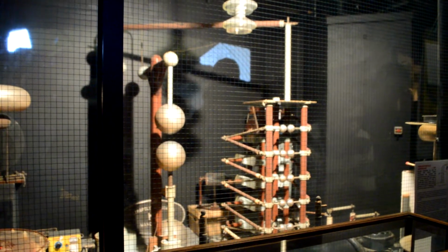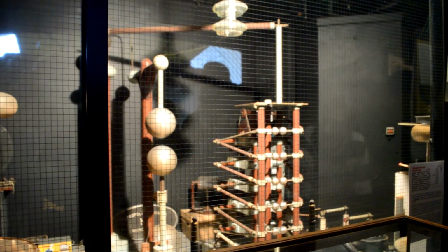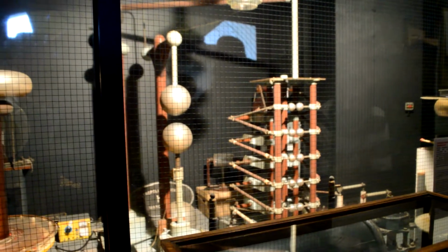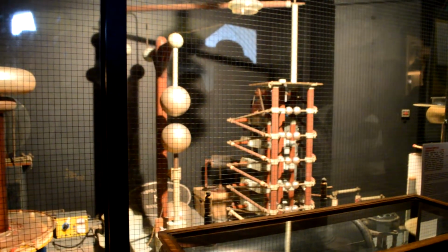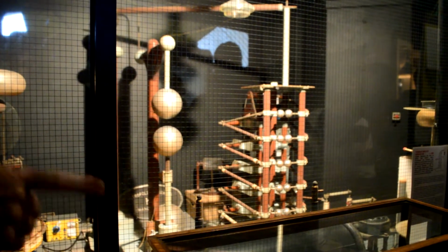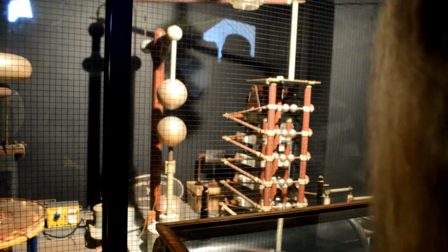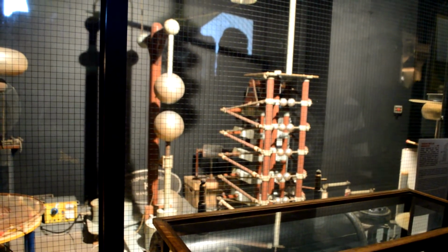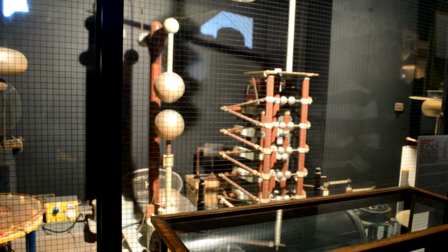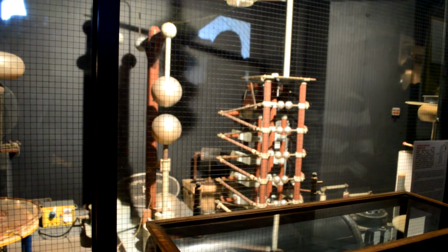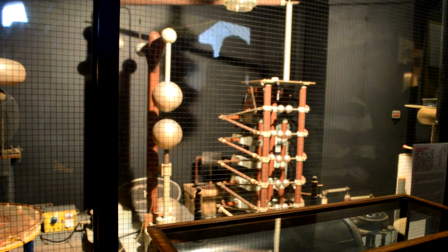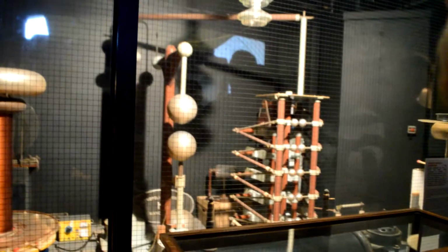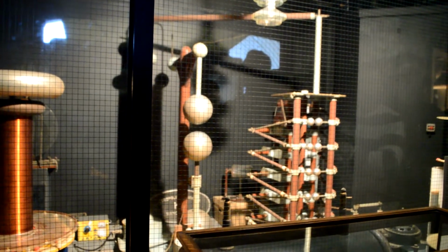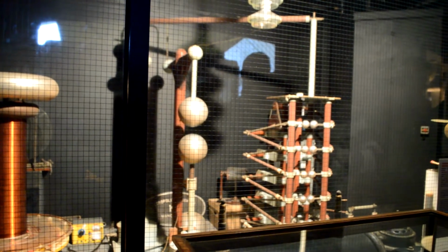International standards still exist, and I always get this wrong because it's changed, but if you look at the thing in a graph or an oscilloscope representation, the principle is that by adding a second set of resistors, which you can see on the schematic diagram on the bench, not only do you control the discharge time, which is to do with the resistance and capacitance time constant of the basic capacitors, you've got the so-called wavefront resistors, which determine the initial rise time to a peak. So, Simon, wherever you are, it's 1.2 microseconds up and 50 down, or 60 down? 50 down, yes. I always get confused with the mains frequency on the decay time.